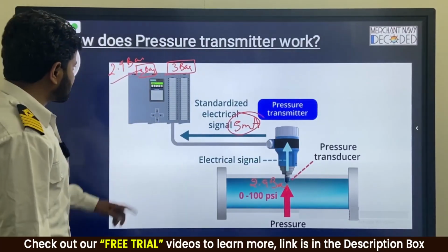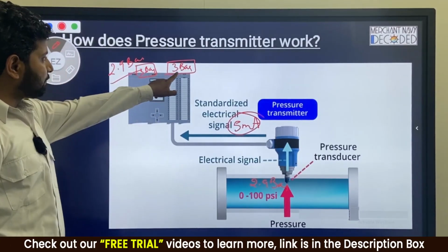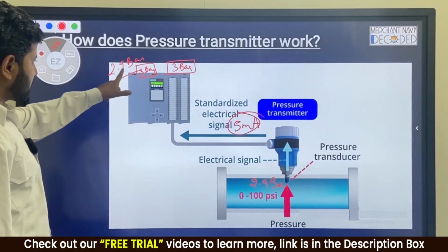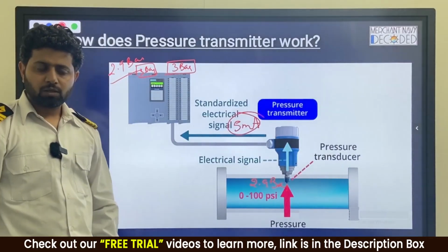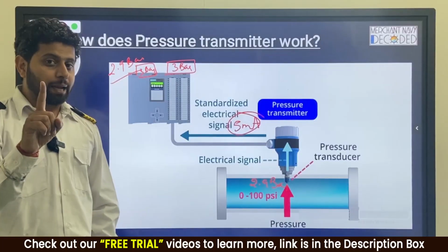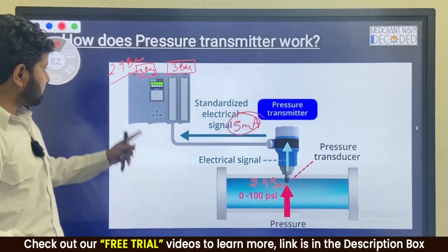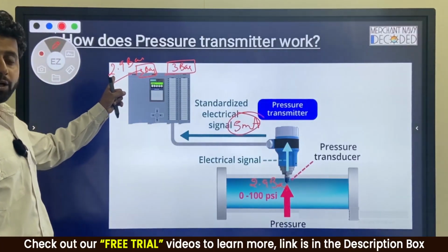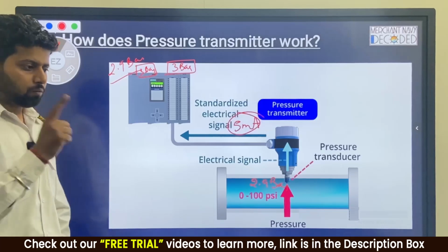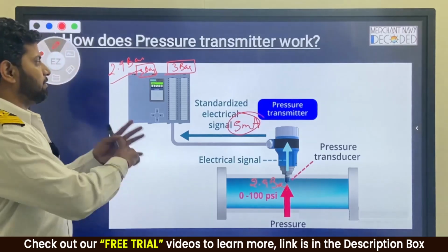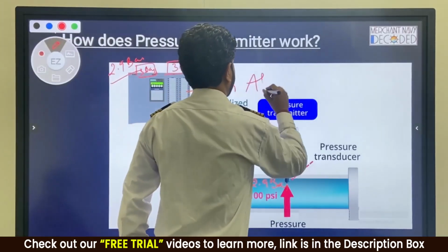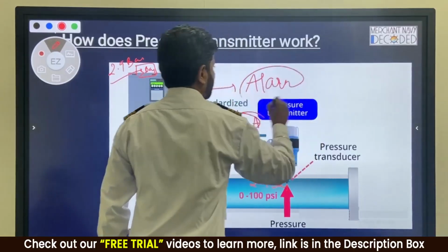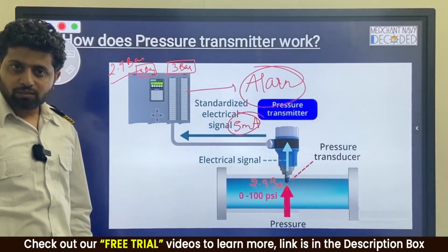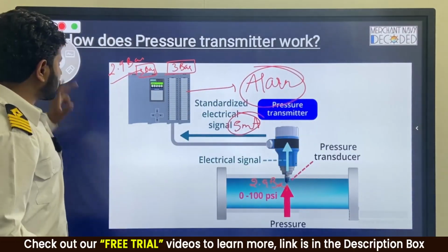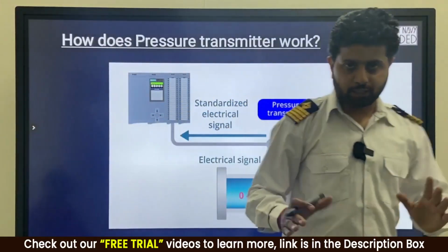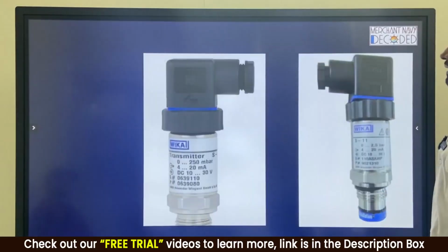So now the PLC says, I have to give an alarm at 3 bar, but the pressure is 2.9 bar. Okay, but there is a time delay of 3 seconds. So if pressure is maintained at 2.9 bar for 3 seconds, 1, 2, 3, I will give an alarm. Alarm coming. Copied, guys? So this is how your automation with pressure transmitter works. Understood? So now let us go ahead.